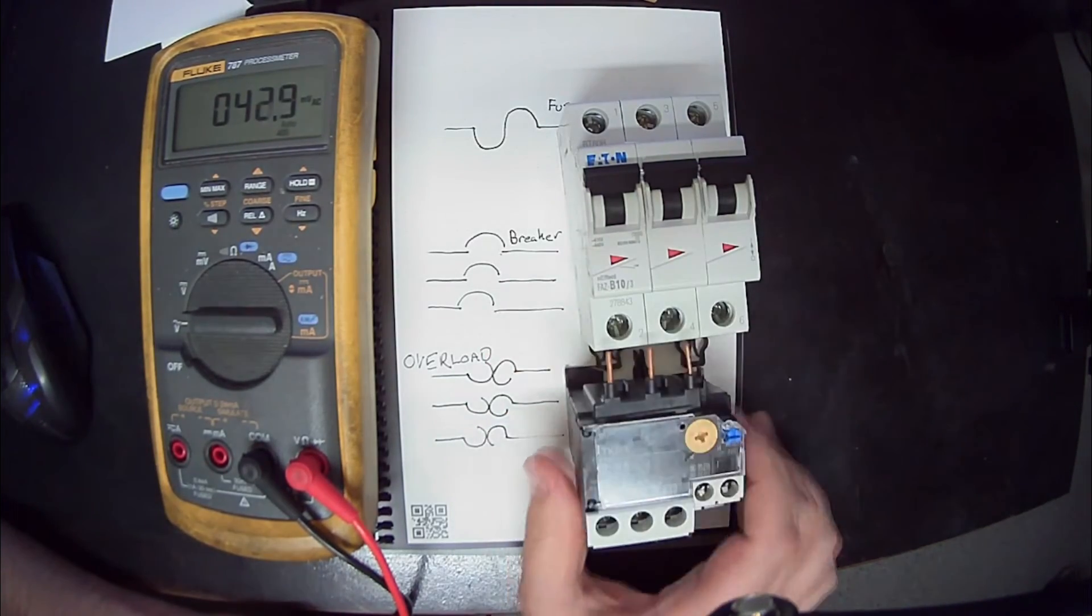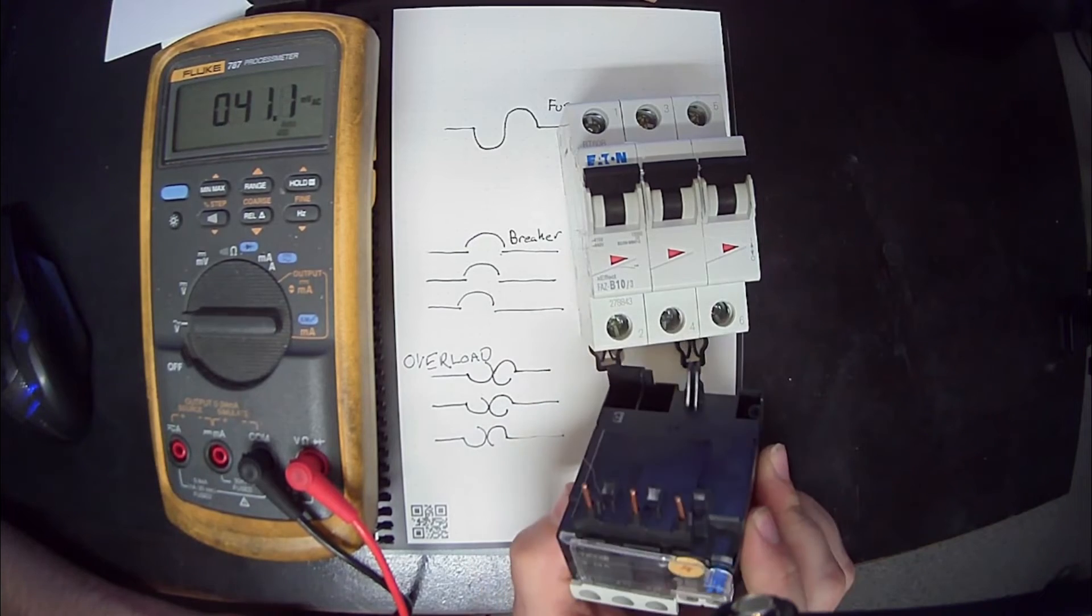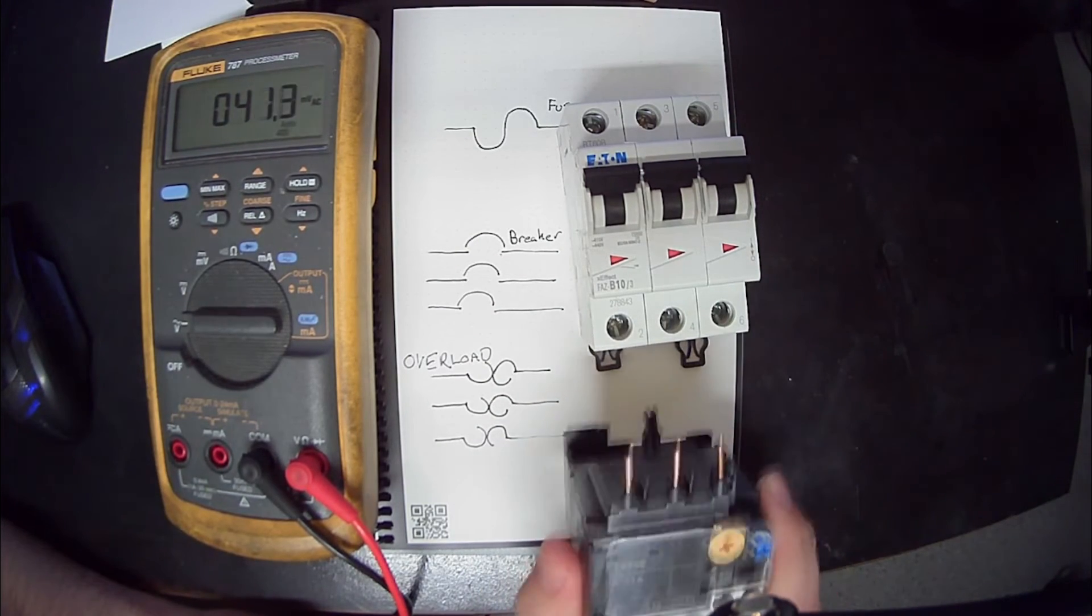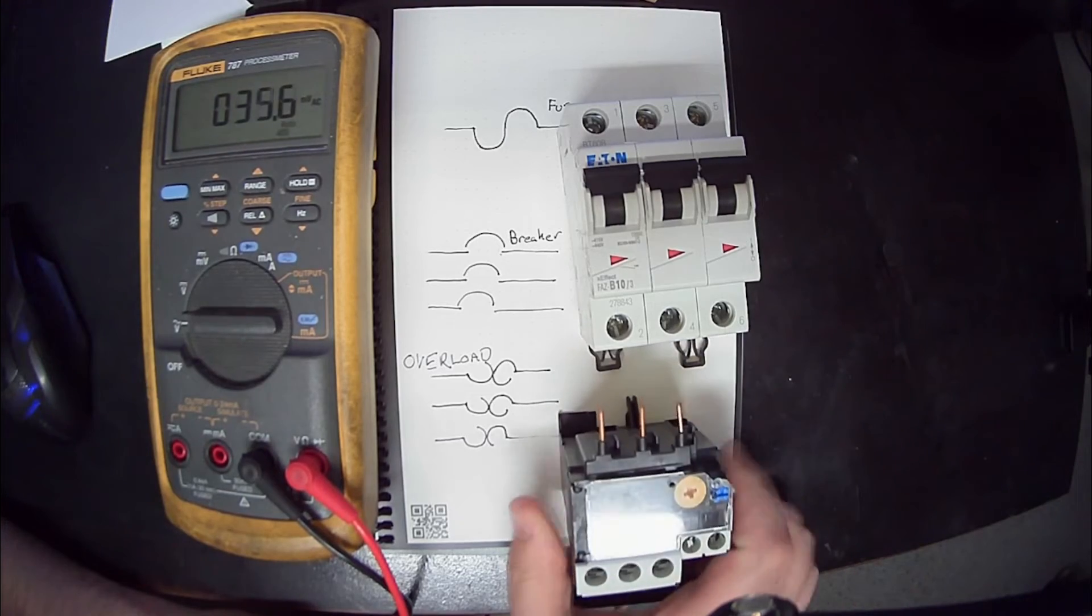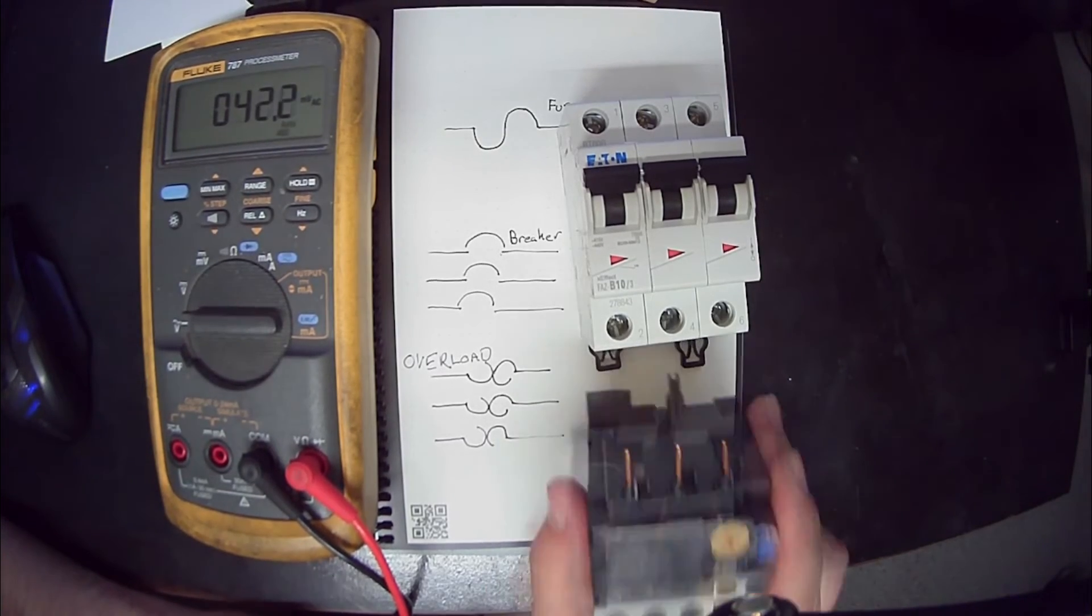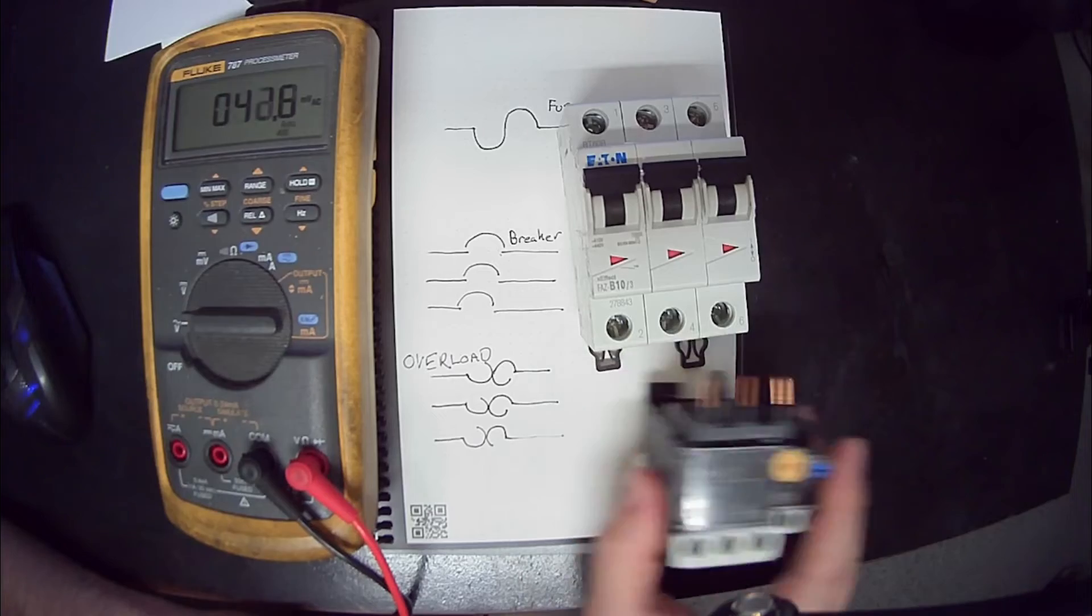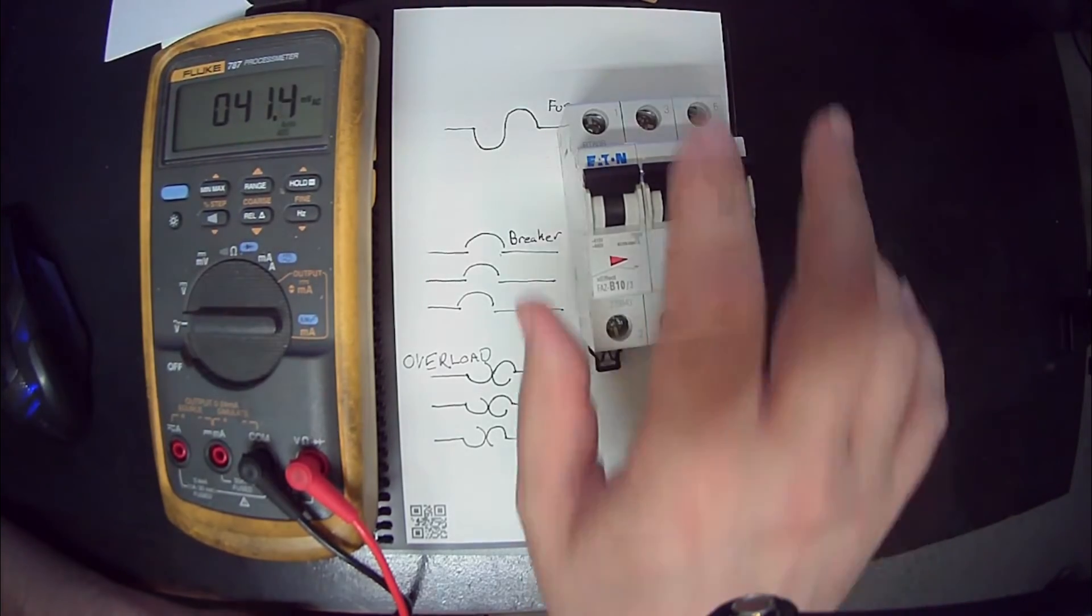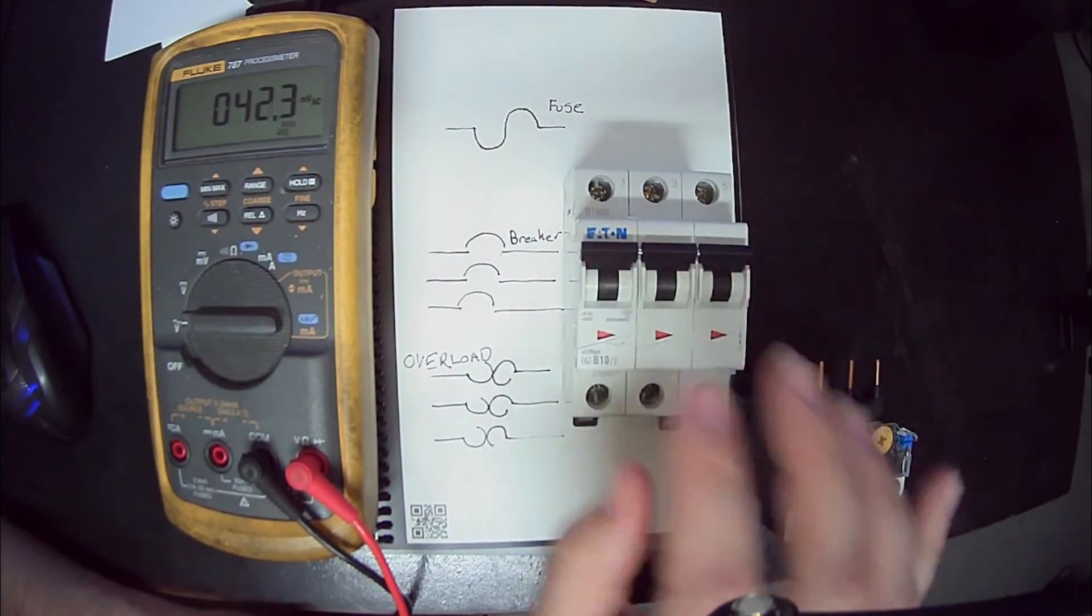It's the same thing that I do with an overload. These go bad - overloads go bad much more often than breakers do. That's actually a pretty common failure. You're going to see that relatively often if you do a lot of work with a lot of motor controls. This is going to be a common failure. Not super super common, but it's still a common failure.